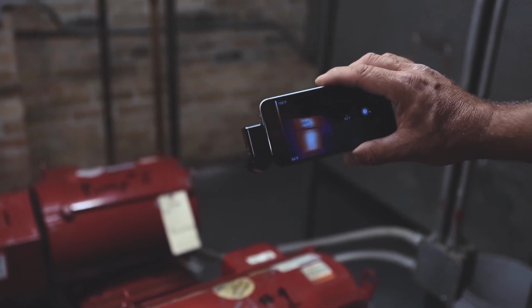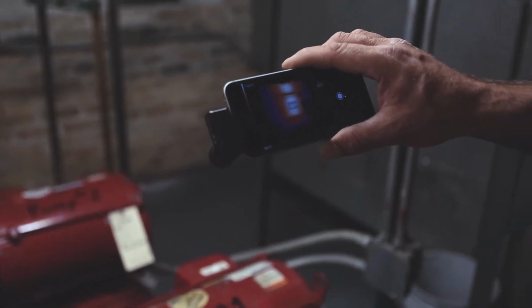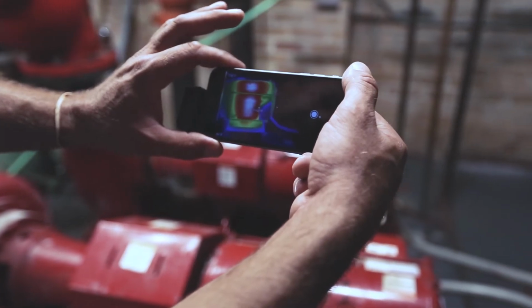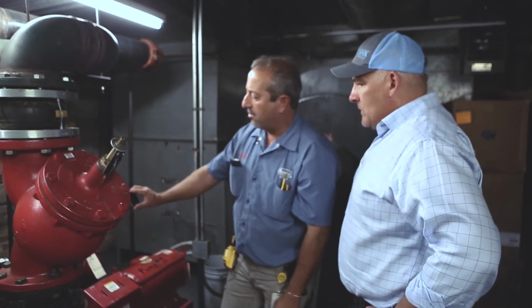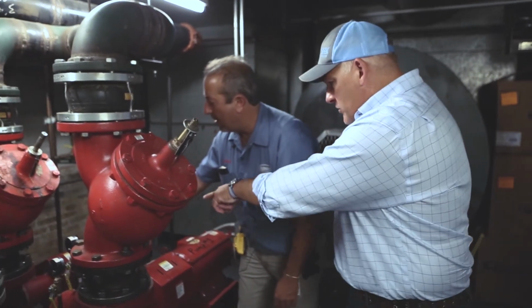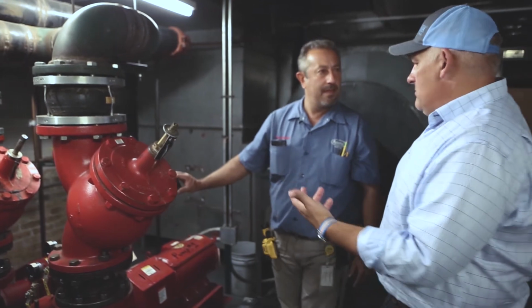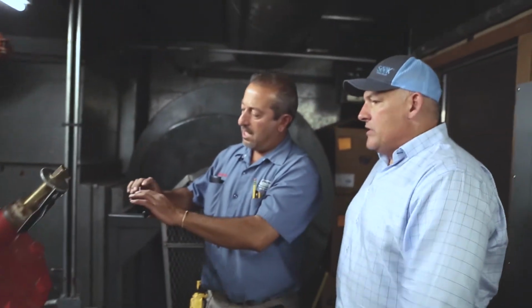It's kind of an even keel there in the center core of the motor where it should be. It gives you actual temperatures, 156 degrees, on the hot side a little bit. If it was really hot, or hot along the shaft somewhere showing red, maybe there's an issue, it's not aligned.